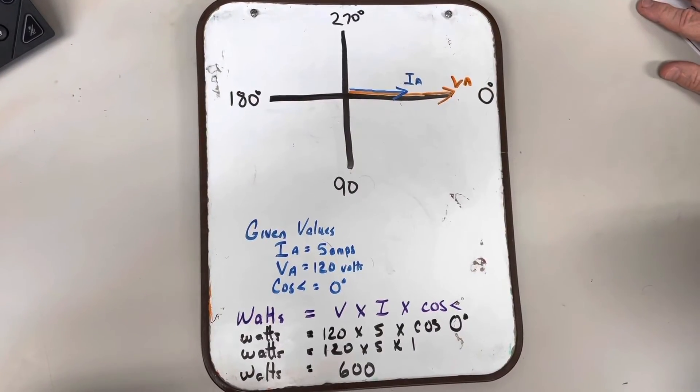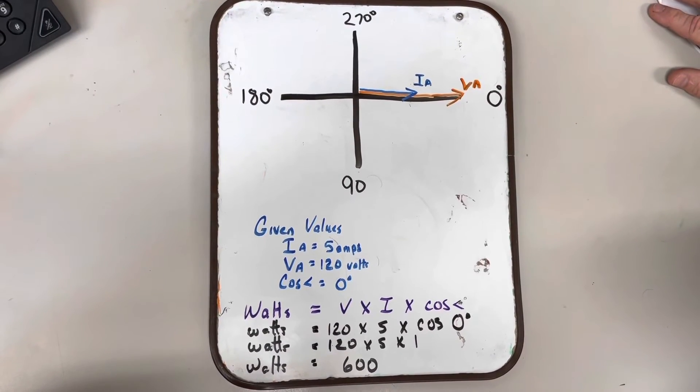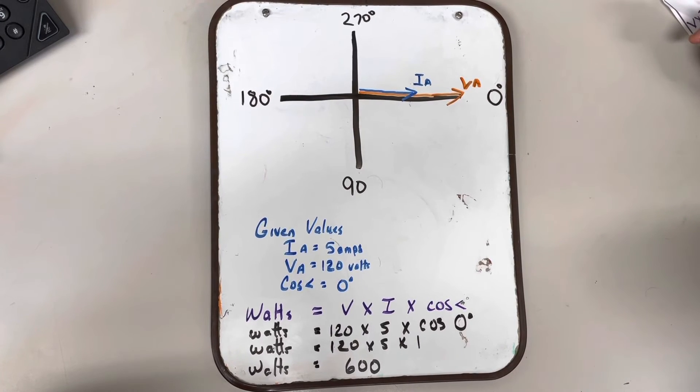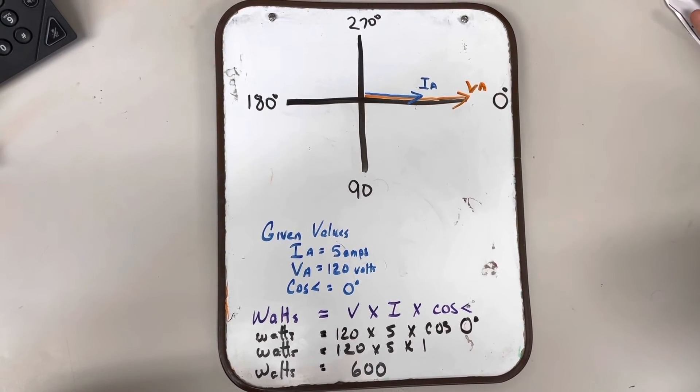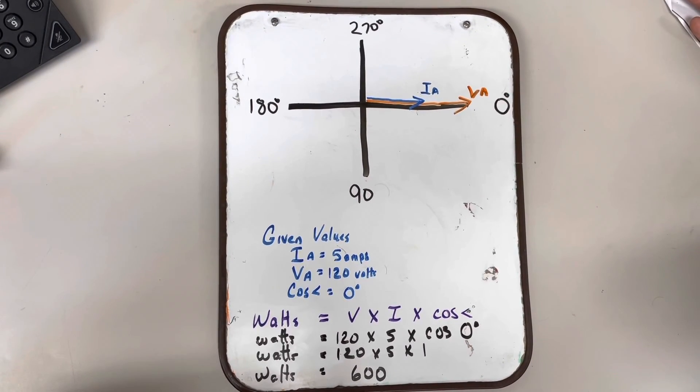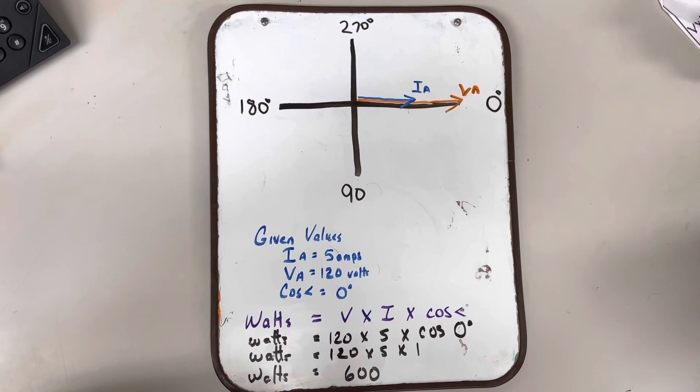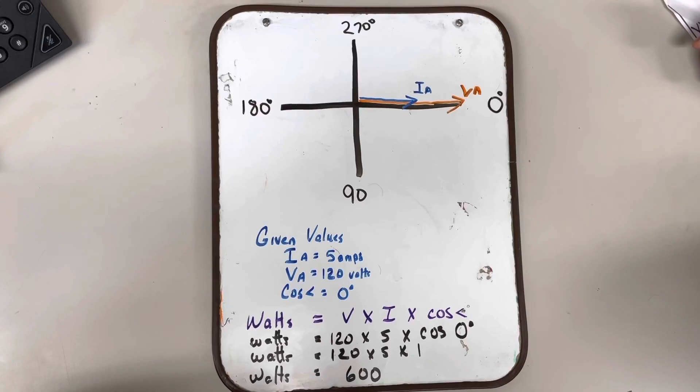Here's an example of the single phase two wire meter that we were discussing earlier. And this is a purely resistive load where the voltage and the current are at zero degrees. With the given values, we need to figure out watts. And the formula for watts is volts times amps times the cosine of the angle. After totaling this up, the load at that single phase two wire meter is 600 watts.